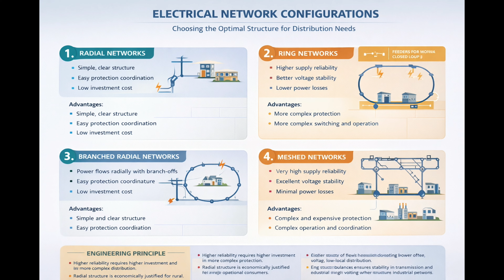Network configuration directly influences fault current levels, relay coordination, voltage profile, operational flexibility, protection design, switching theory, and others. You must always align the chosen network structure with those parameters. There is no universal best configuration. The optimal solution depends on the load density, required reliability, and available budget.